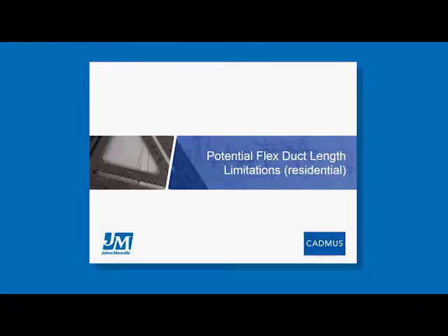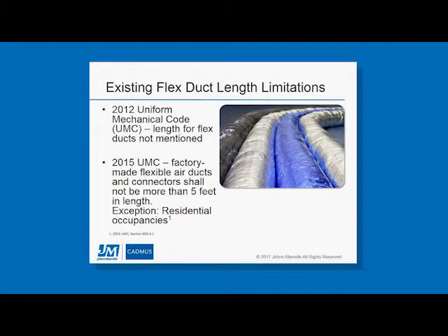Okay, thank you very much, Eric. One of the potential code changes being considered in 2017 that had implications involved a restriction on flex duct. This is governed by the International Association of Plumbing and Mechanical Officials, involving the Uniform Mechanical Code. In 2012, there wasn't a restriction on the length of flex ducts. However, by 2015, a restriction was put in place in commercial buildings. I believe the reasoning is that they felt a lot of the installations of flex duct, particularly when they were long, tended to be crimped and compressed, so that they weren't very efficient.